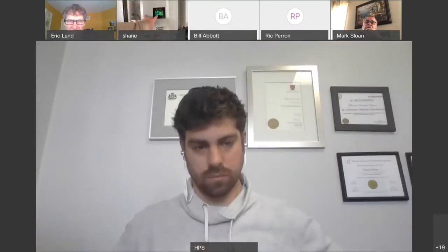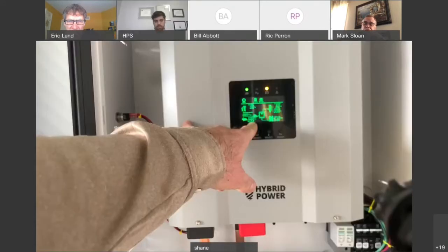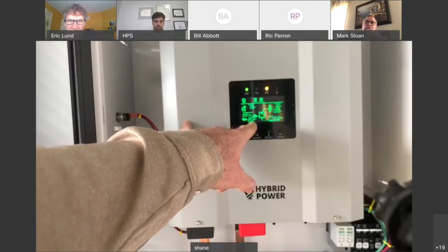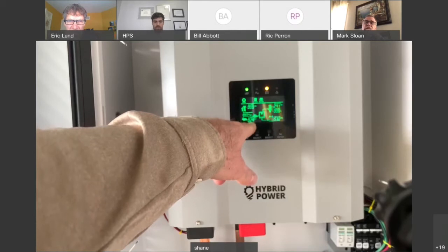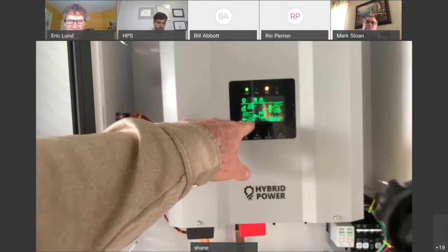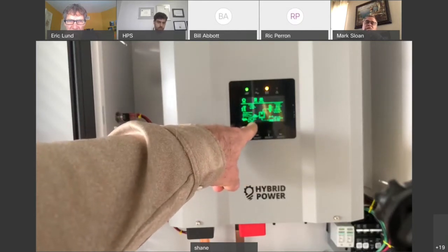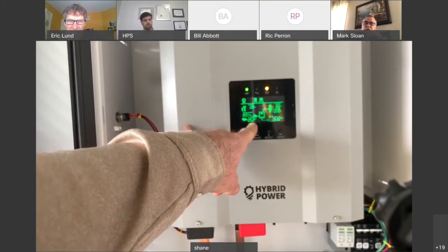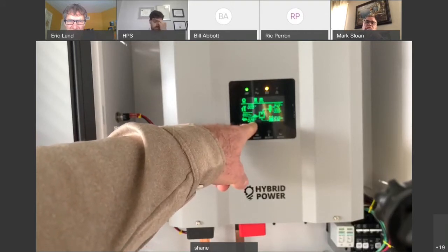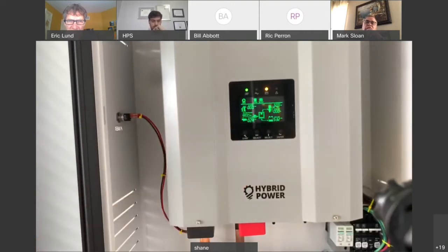So now we see our PV indicators coming on. Our DC bus is going to start charging on our PV side. We have 95 volts coming in, and it drops down to 2 amps to show you. Now, when it says 2 amps, that's on the PV side, so that's on the high voltage side. So we're charging at 2 amps at 52 volts. Okay, so we're in a low light condition. So in a low light condition, the MPPT will track harder at a lower voltage. This is just to create a more efficient tracking than trying to track at a higher voltage.